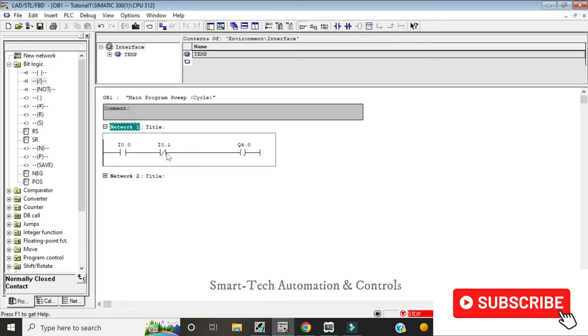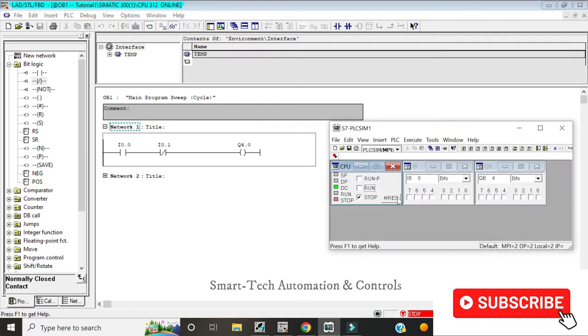So in this case, our normally closed contact will act as a stop button. Let's simulate this and see how it works. Again, I'll download the program to my simulator. Then I switch it on. I put it on run mode. Let's observe what happens when I give a signal to my first input, which is I0.0. You can see that the coil is energized. But if I give a signal to this other input, which is I0.1, it is going to break the contact and our coil will no longer be energized. So if I give a signal to 1, you can see the coil, it's no longer energized.